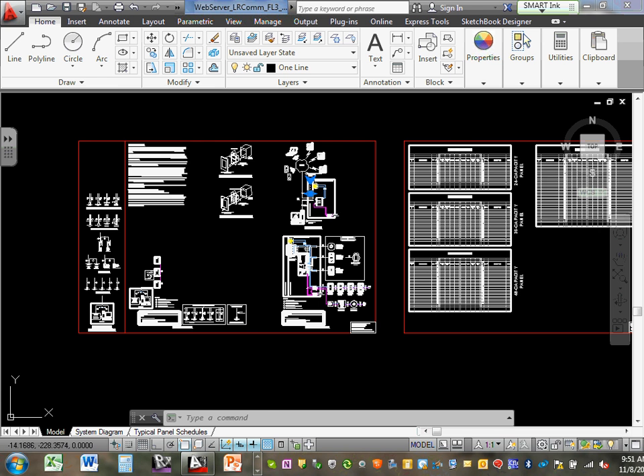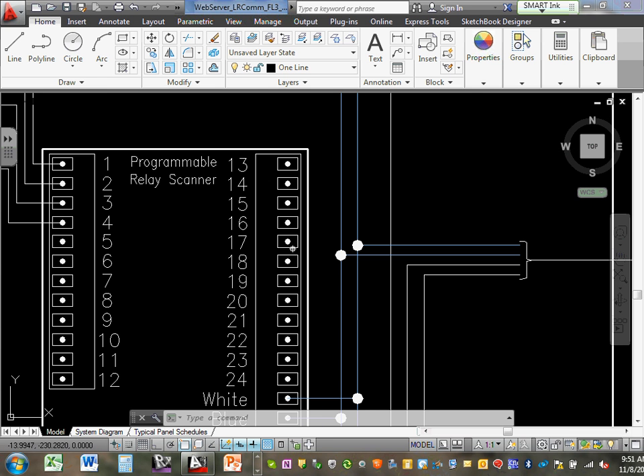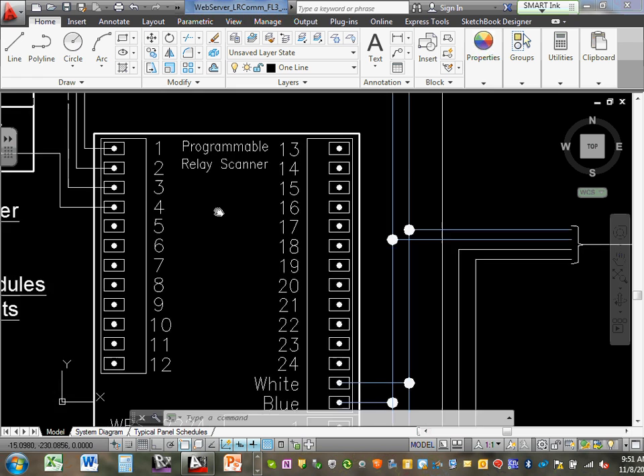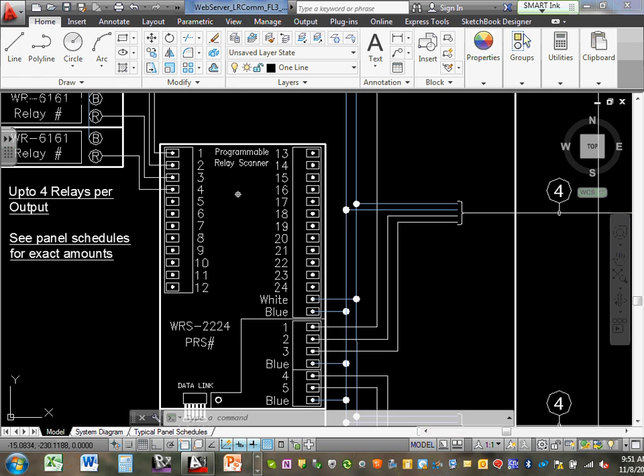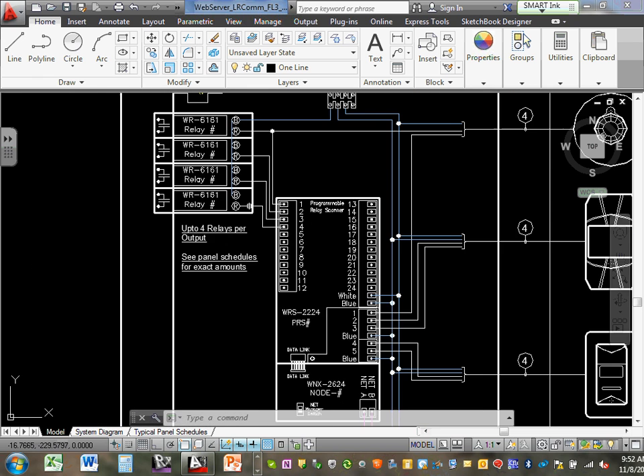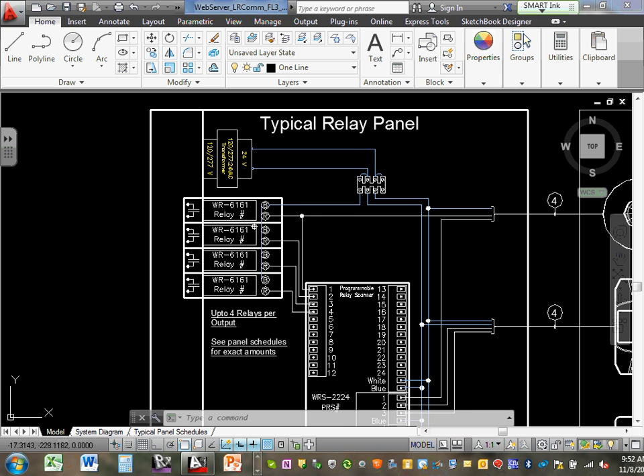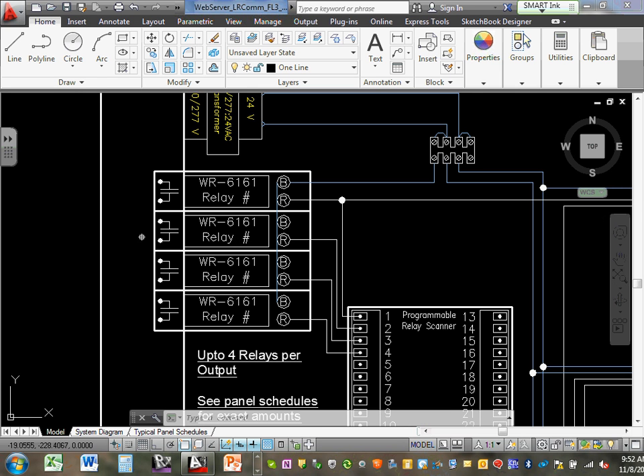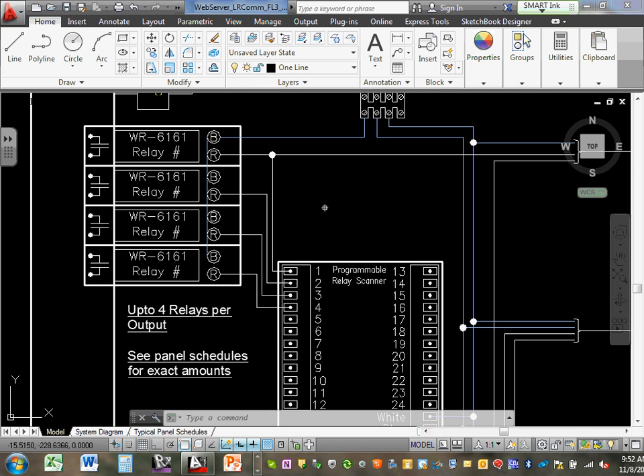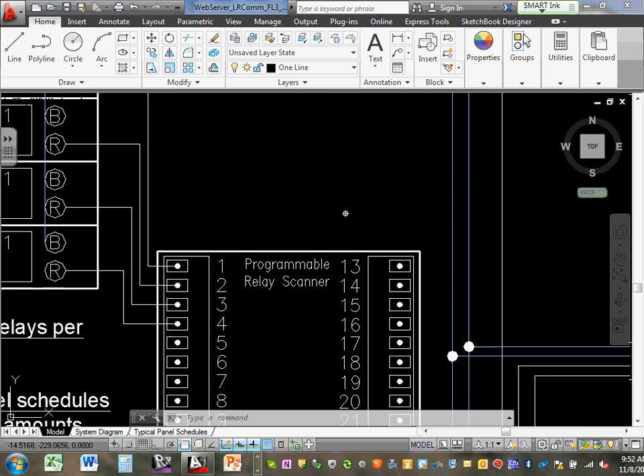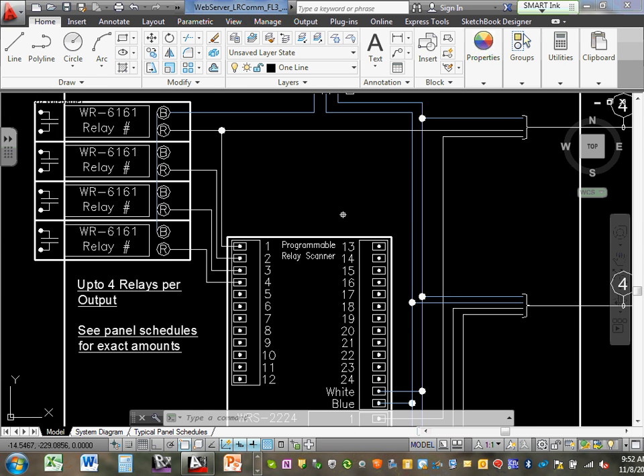So then when we break that panel down into multiple relays here, go up a little bit, there we go, yep. So now I've taken these 4 relays just as representative, and I've tied those directly to an output. That's in a very simple system. So I've tied those together in a simple output on a scanner, and now I can program those outputs to do whatever I want them to do. I can combine them. 1 and 2 can do the same thing. 1, 2, 3, 4 can do the same thing. 1 and 5 can do the same thing. It doesn't make any difference, right? That's all programmable from that point out.